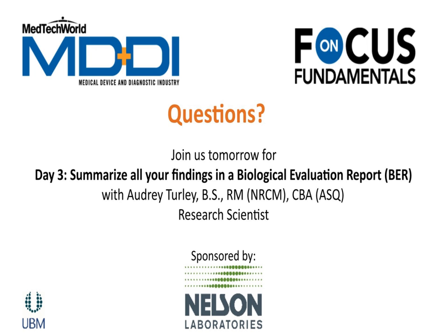In general, if you're looking to justify out of biocompatibility testing with a new submission, we're going to look at the whole device that has patient contact. But if you're doing extractable leachable testing to address a change to an existing device, and want to see what new risks or new chemicals come off of the device that may cause an adverse effect in a patient, then you could just look at that component.